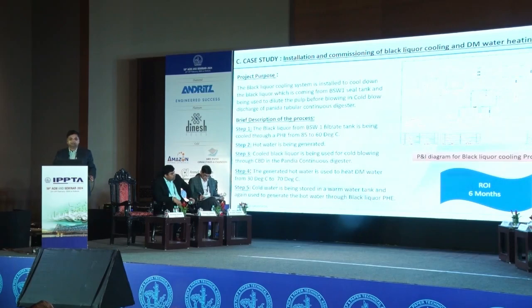This black liquor is cooled by water, so hot water is generated. The cooled black liquor is used for cold blowing. The hot water which is generated is used to heat the DM water from 30 to 70 degrees centigrade. The cold water is stored in a warm water tank and used again to generate hot water through the black liquor PHE. This project has an investment of around 2 crores and an ROI of around 6 months.